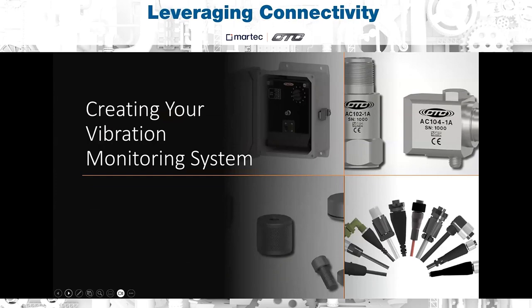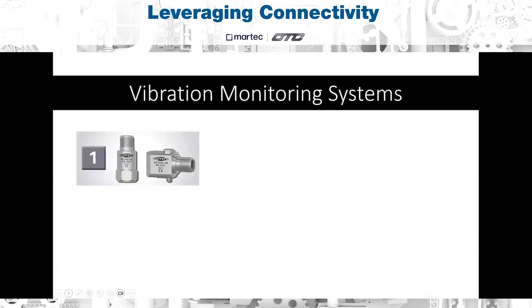So let's get into the components and the steps that can be taken for creating your vibration monitoring system. The first step and the first component are the sensors. Sensors are arguably the most important component of every vibration monitoring system, as everything starts at the sensor. Sensors are mounted on rotating equipment to measure the machine's vibration levels. These sensors are capable of converting the mechanical motion of vibration into a measurable electrical signal. That electrical signal can then be used to predict and prevent potential failures in the piece of equipment. CTC offers a wide variety of sensors that I will dig deeper into in a later slide.